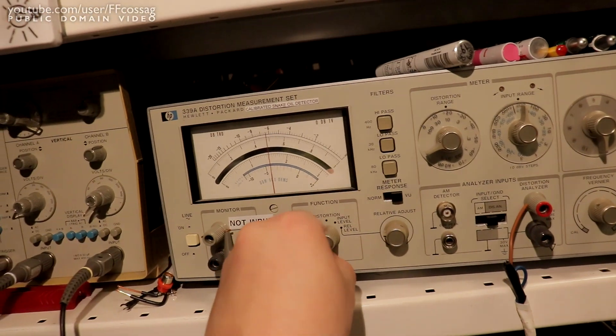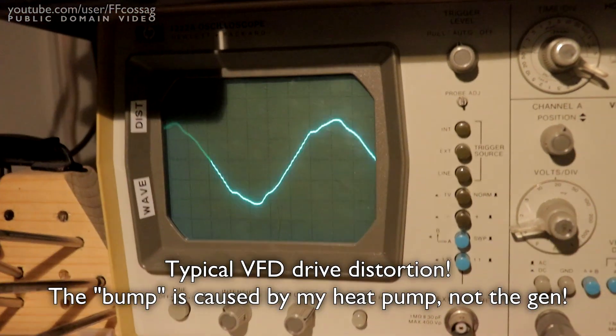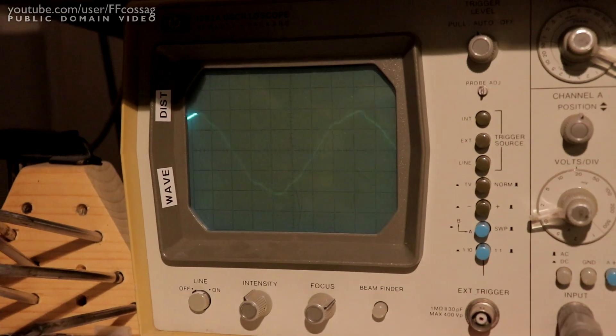As a final note to this video, I've just finished the proper generator hookup, so we can actually see the output performance. It's not actually super — I was expecting a bit better — but we are going through a fairly long extension cord and we're powering the heat pump, which is a 15 kilowatt inverter. We have a distortion waveform here; looking at the output waveform, it's a bit jagged, not a perfect sine wave, but certainly leaps and bounds beyond what a cheaper genset would do.